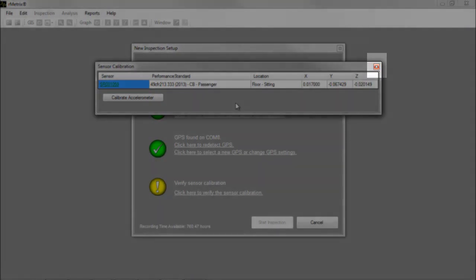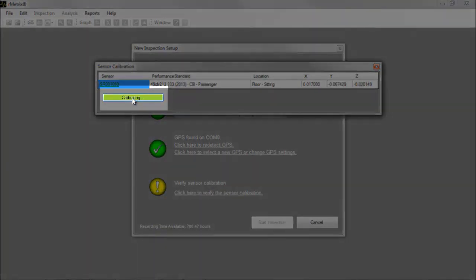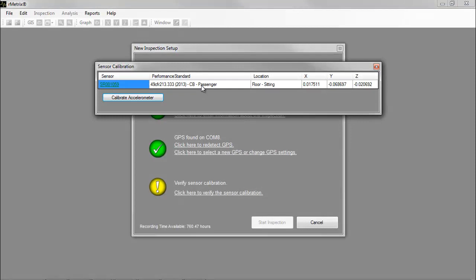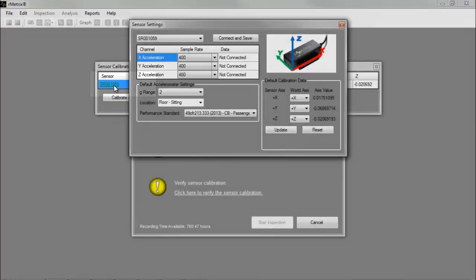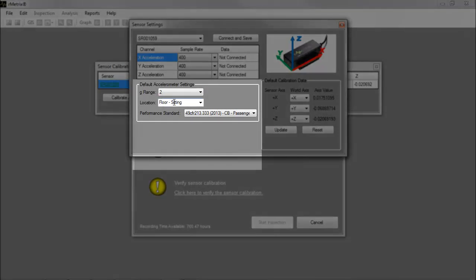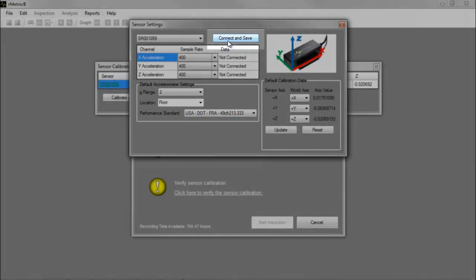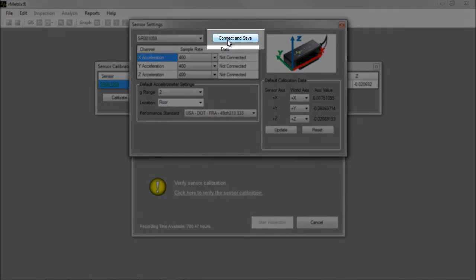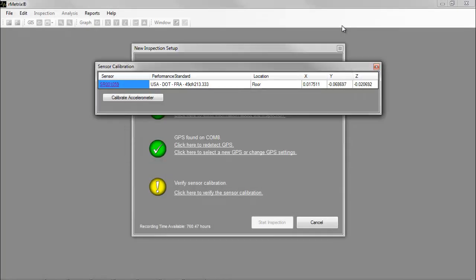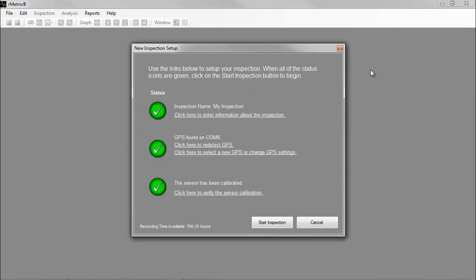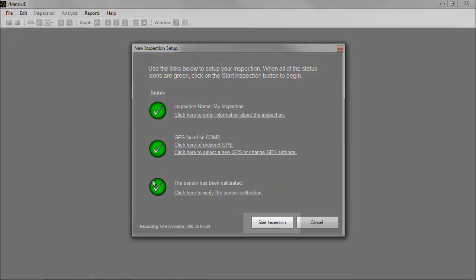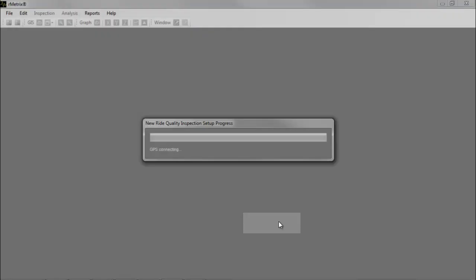To update the calibration, click on the Calibrate Accelerometer button. To change the performance standard, location, or G-range of the sensor, click on the sensor name. Modify the default accelerometer settings. Click on Connect and Save. After data is streaming, click on the Disconnect button. Close this window and this window to continue. With these 3 green check marks, you can now click on the Start Inspection button.